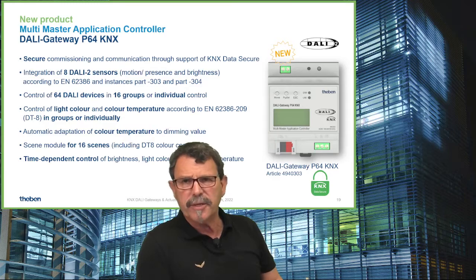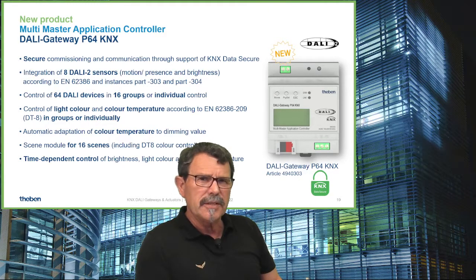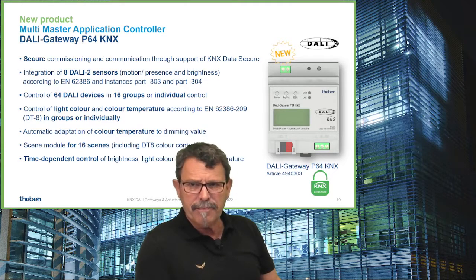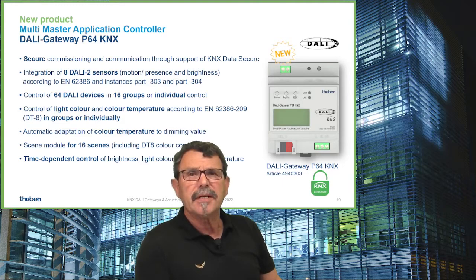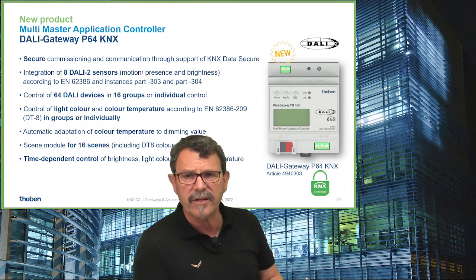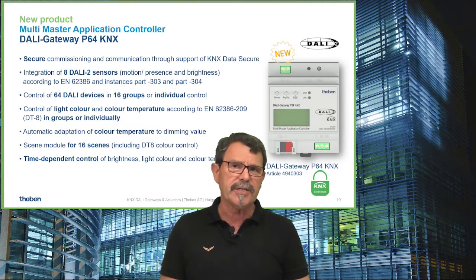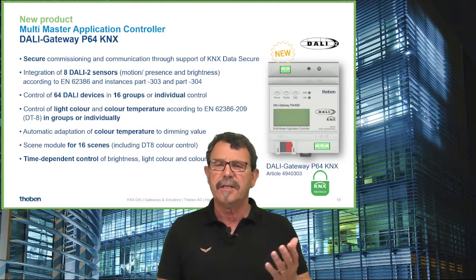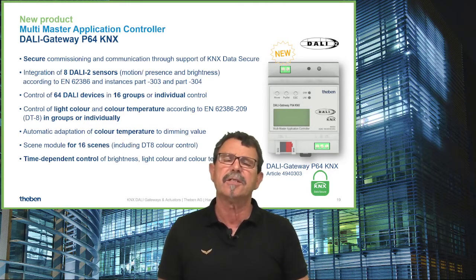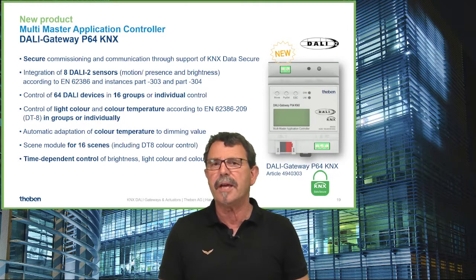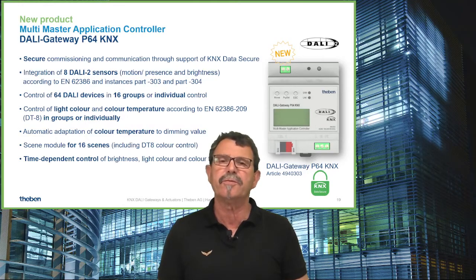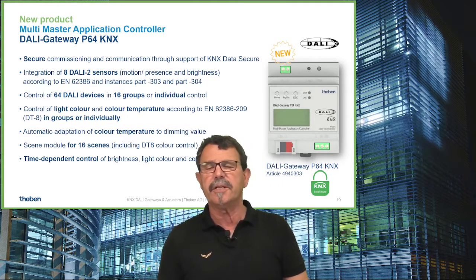So in general, frankly speaking, we're using the ETS application with the DCA app, which we need. The DCA app you get from the KNX store. There you'll find for free in the download area the Tapko app for the DALI gateways. You just have to register, download it, and install it in the ETS, on the right hand side at the bottom, where there are the areas for apps and licenses and so on. You open the app, integrate the new app and enable it, and that's it. Then you can operate and do the configuration, as you will see in a few seconds.